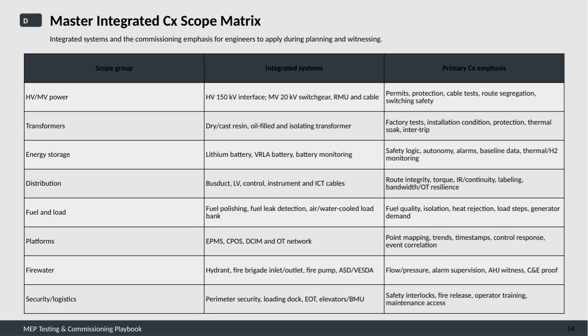Here we have the Master Integrated Commissioning Scope Matrix, an essential guide for engineers focusing on integrated systems during planning and witnessing phases. It breaks down the scope groups by system type, each with its primary commissioning emphasis. Starting with HV/MV power systems. This involves high voltage interfaces and medium voltage switchgear. The key checks here are permits, protection mechanisms, cable testing, proper route segregation, and ensuring switching safety.